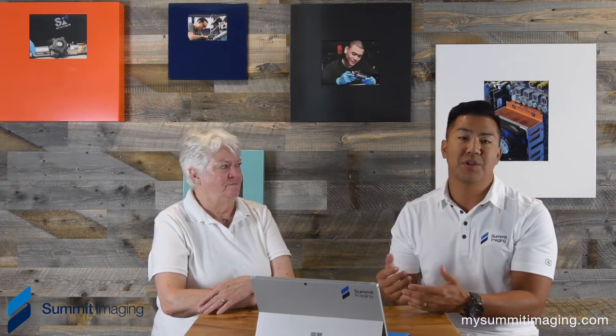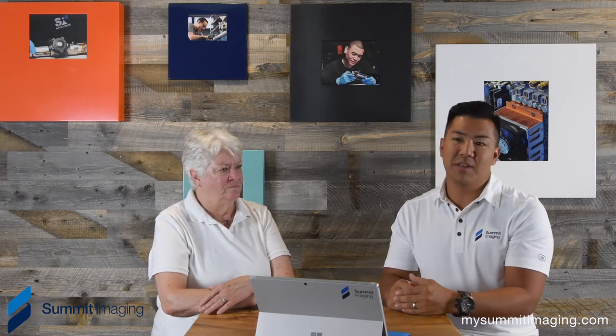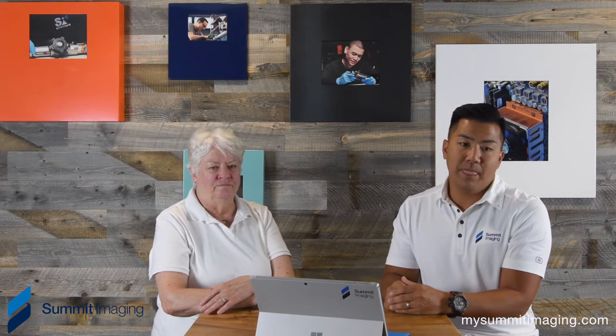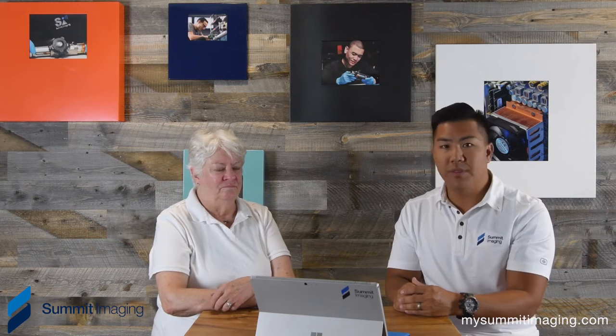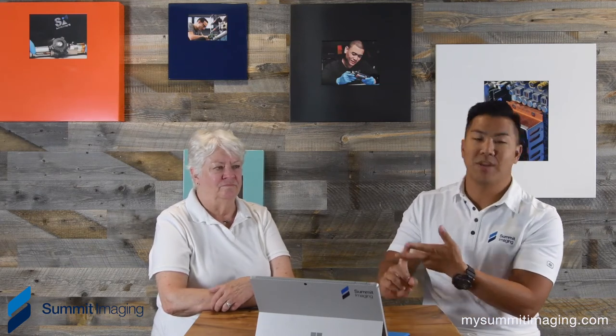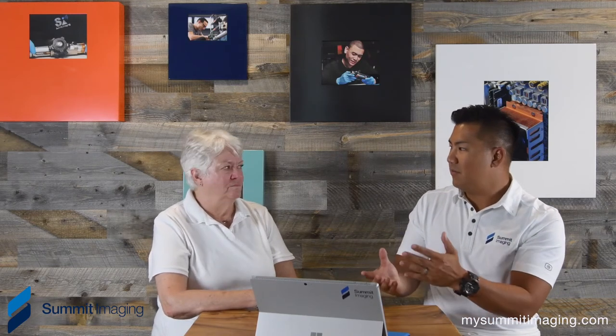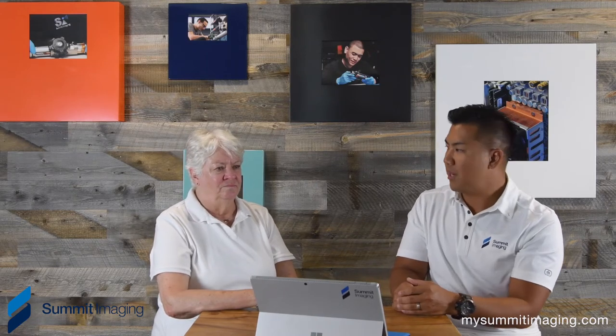Today we wanted to talk to Carolyn about her experience with improperly remanufactured parts used in transducers — hidden inside transducer repairs. At Summit Imaging, we don't use any remanufactured parts because it doesn't preserve the safety and performance of these transducers. Carolyn has experience with remanufactured crystals and remanufactured cable assemblies, and how they've frustrated her working process of trying to give really high quality patient care.